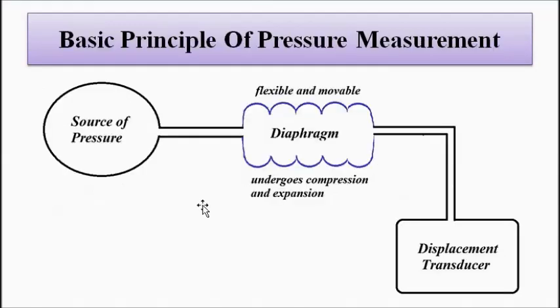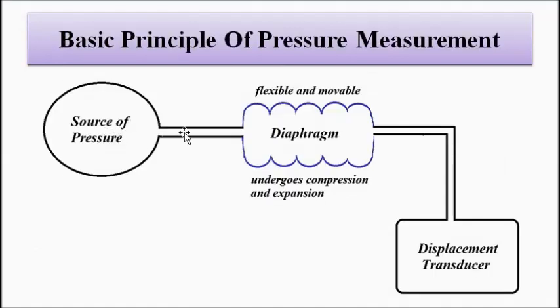The basic principle which involves is that we connect a diaphragm kind of a setup to the source of pressure, the body part where pressure is to be measured. When the diaphragm is subjected to pressure, it undergoes compression and expansion which causes the displacement transducer to respond to that fluctuation, that compression and expansion, and gives us a signal.